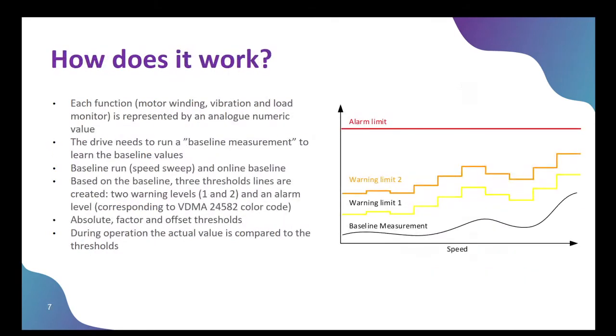But then it's not enough to detect this. It's also important to understand how you detect, because the way this works is that the drive learns a normal condition, a so-called baseline, and during this baseline measurement, the information is stored in the drive, and after that, there are set some thresholds. So we set 3 thresholds corresponding to traffic light: yellow, orange, and red. Yellow is the first warning limit, and it means something changes. Orange means it's a change and we need to address it immediately, and red is then the functional failure. Red is when we need to stop the application from running.